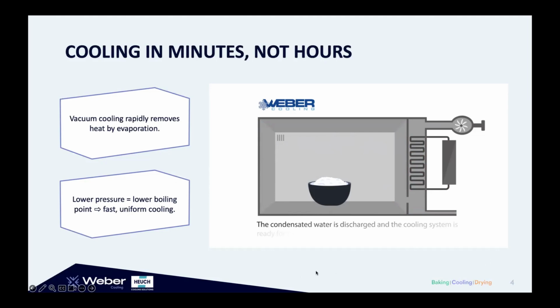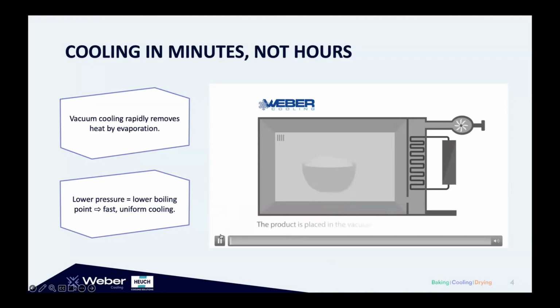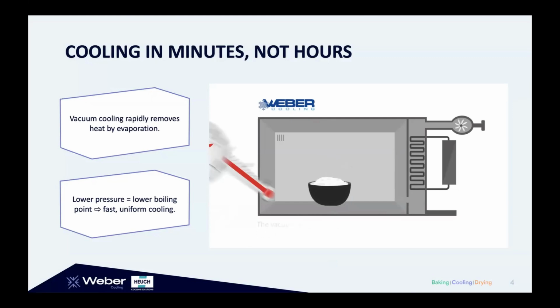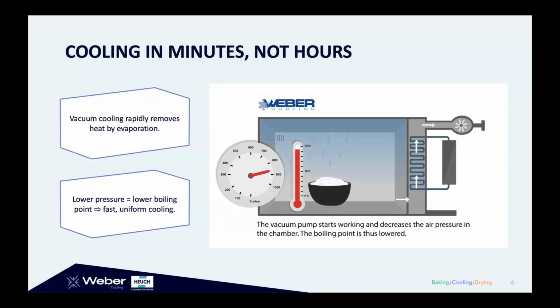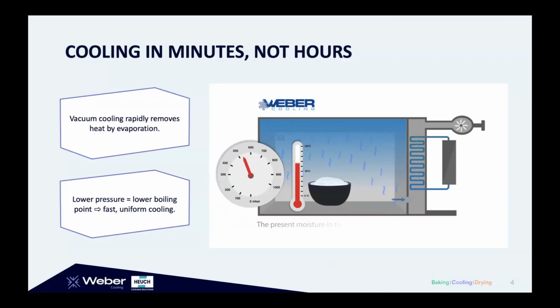To go to low temperatures, the glycol mix will need to be at -5. So what happens is that when all the moisture or the heat is released from the product, it's directed to the heat exchanger. Esther, maybe you can run the video again. It's directed to the heat exchanger. This heat exchanger absorbs all the moisture so that the moisture does not go through the vacuum pump, because the vacuum pump does not like moisture. So it's absorbed by the heat exchanger.